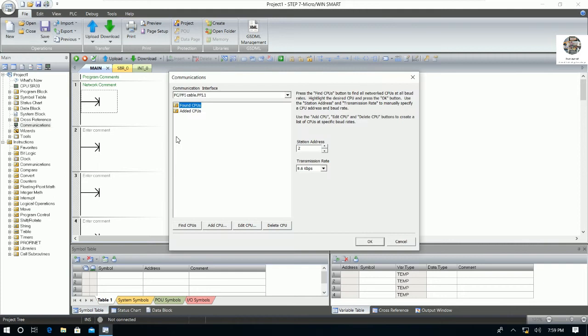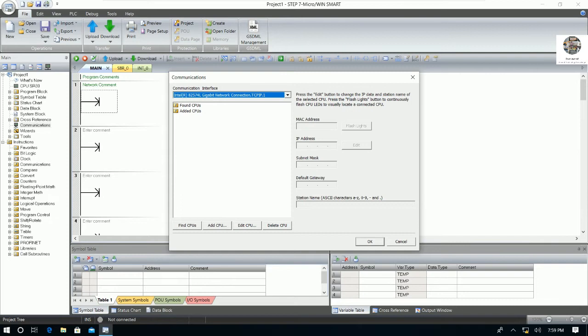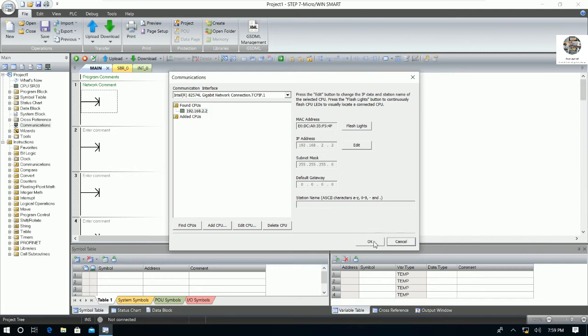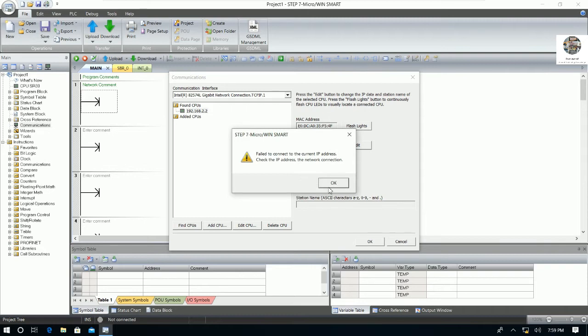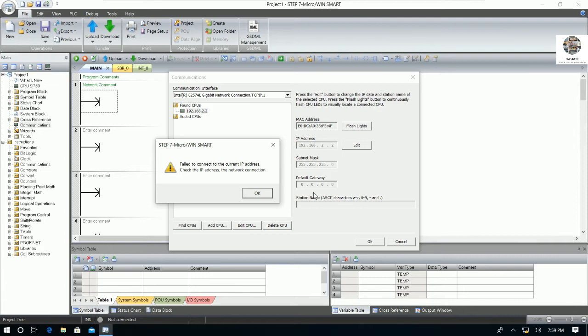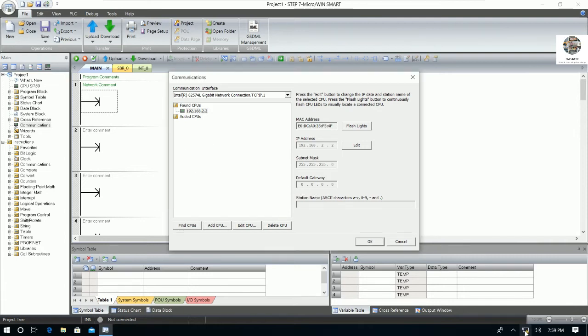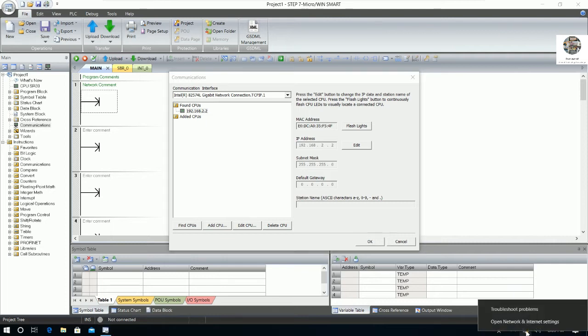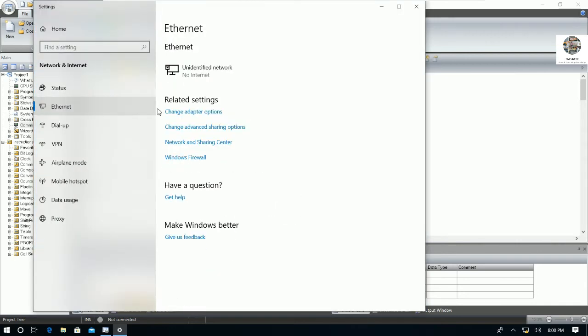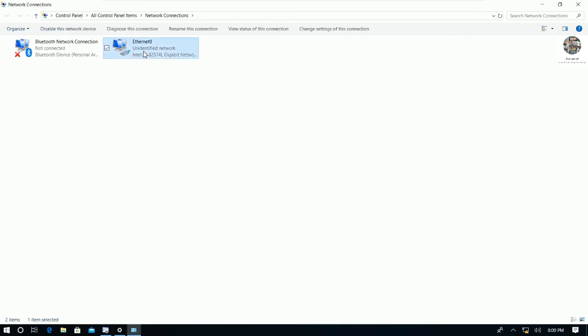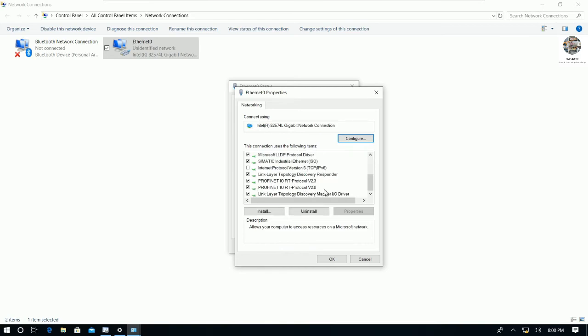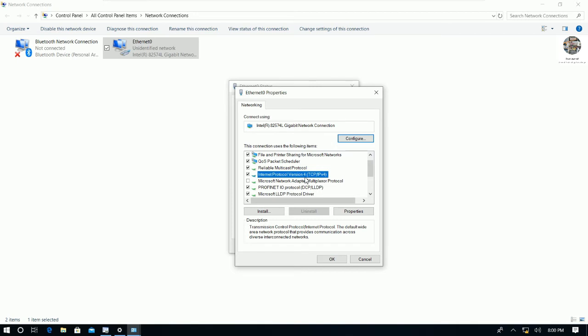We can also test with the CPU IP address by going to the internet LAN cable settings. Here is the IP address of the PLC: 192.168.2.2. If we click OK it will show an error because we have not yet set the temporary or manual IP address of our computer. So let's go set the manual IP address — open the network settings, go to Ethernet, go to the Ethernet adapter and go to Properties, then IPv4.